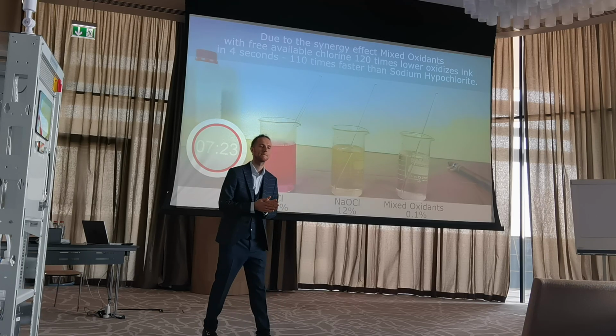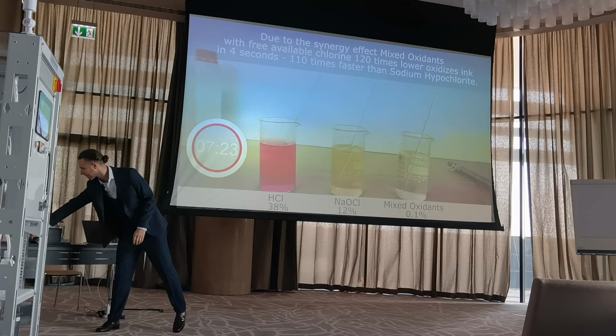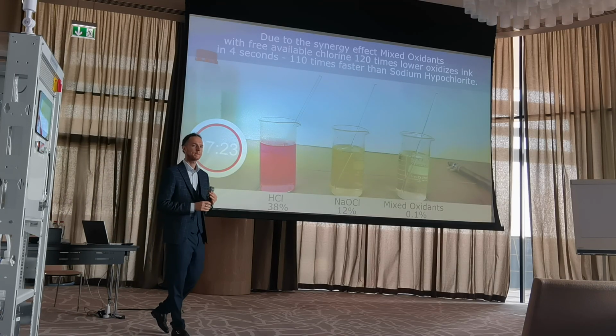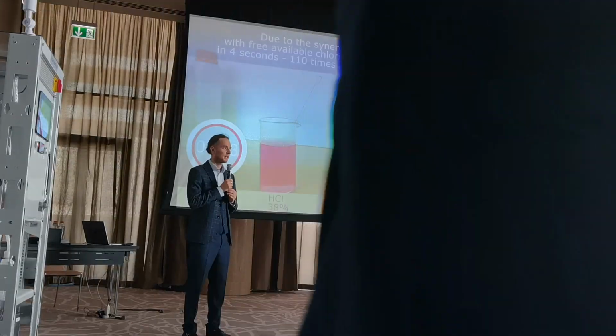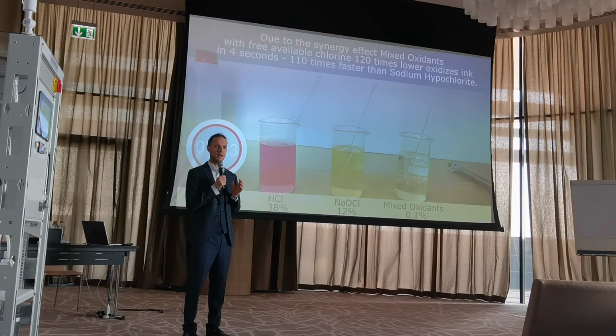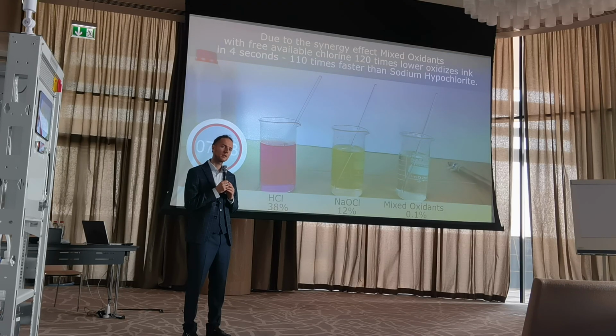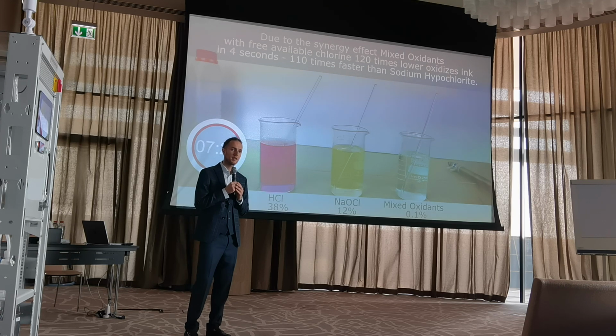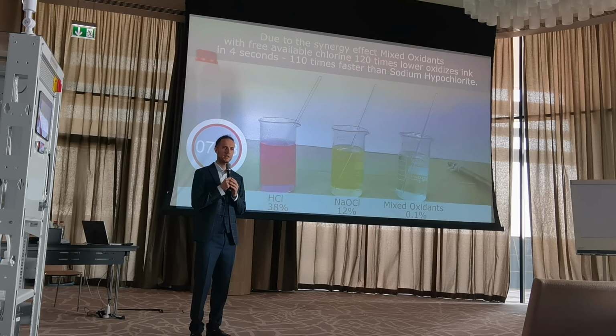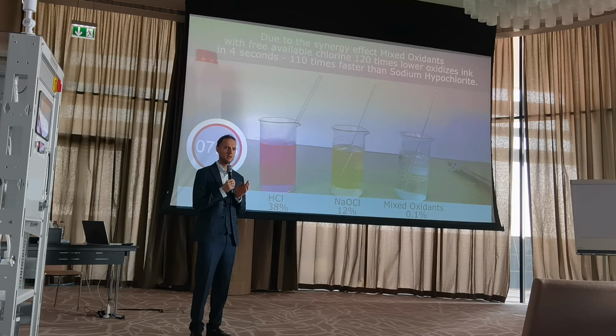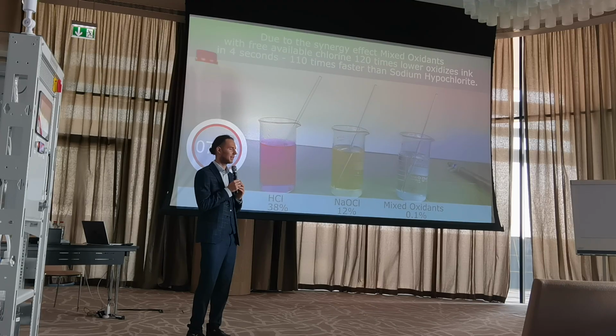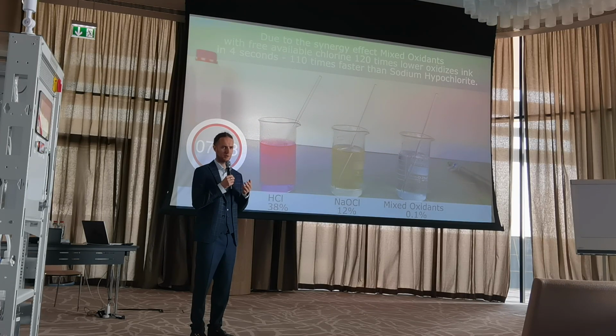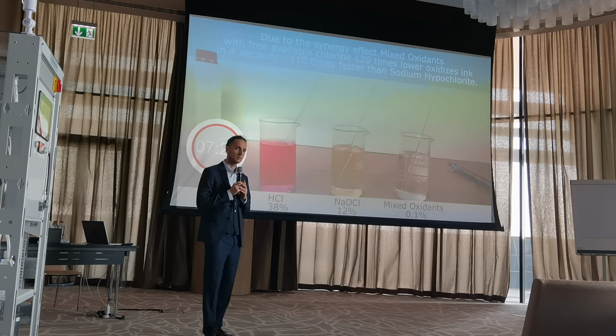Just one question: how could we control the dosage for the mixed oxidant? By active chlorine, we measure everything by active chlorine. Do we have an analyzer or sensor for that? Yes, this is exactly the same sensor which you use for chlorine gas or sodium hypochlorite, the same sensor which measures active chlorine. You don't need anything special, like for chlorine dioxide you need a specific sensor. Here, no, just a sensor for active chlorine. It is installed in the network, in the potable water, and you can control the residual chlorine, and we can see on the monitor what is the dosage.